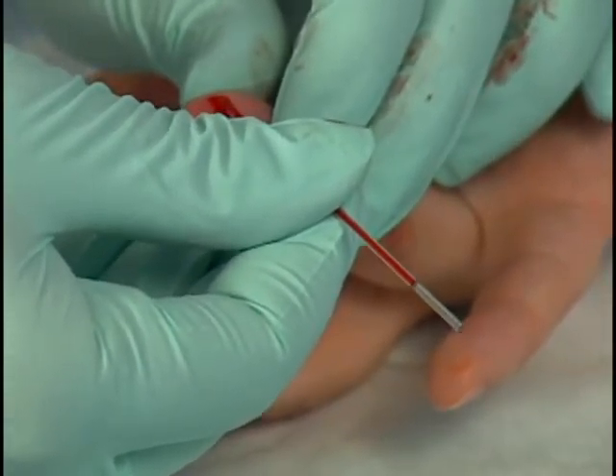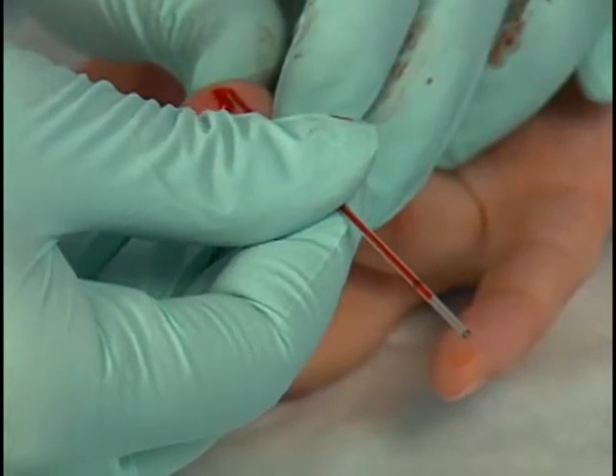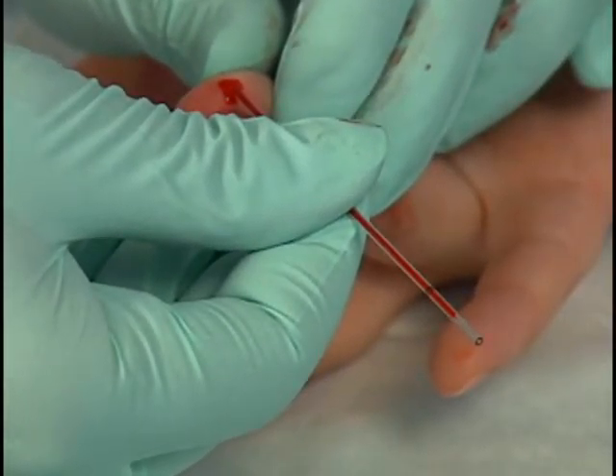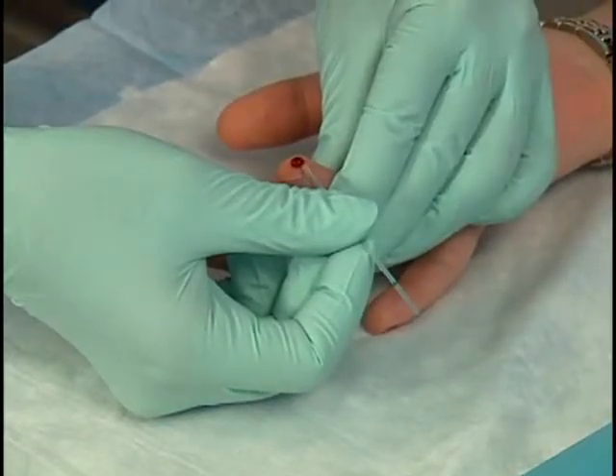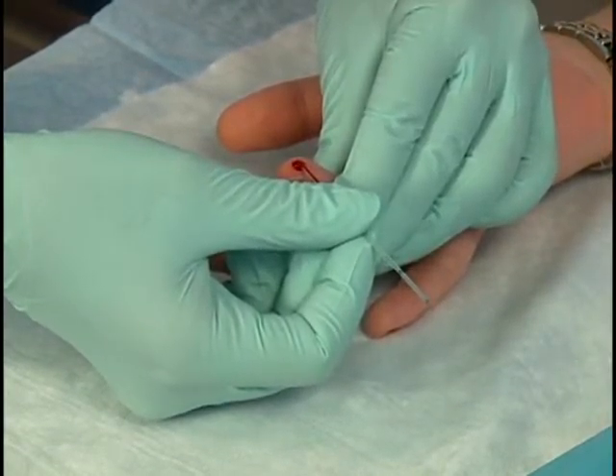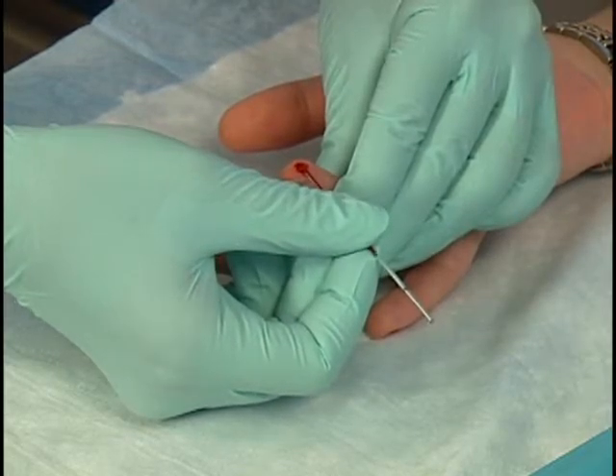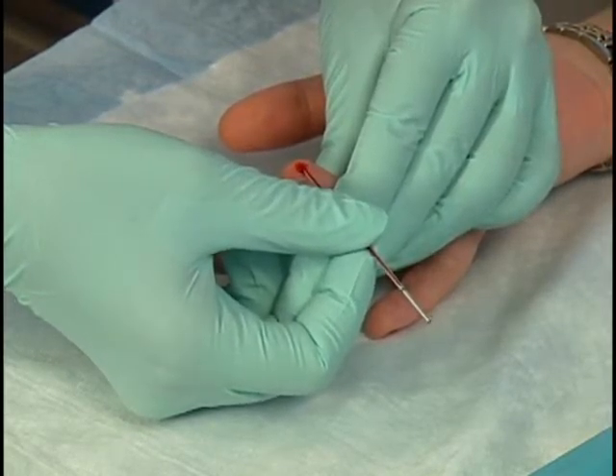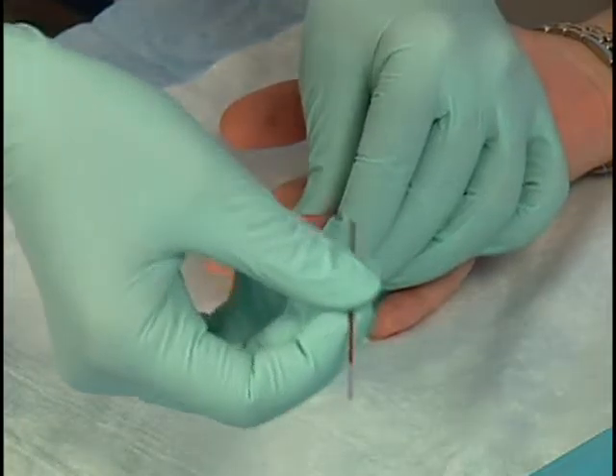If you go past the black calibration line, you have overfilled the tube. If this occurs, discard the tube in a biohazard sharps container and fill another tube. Overfilled tubes result in falsely high test results. Fill a second tube using the method just described. The hematocrit should be performed in duplicate to ensure accurate and reliable test results.